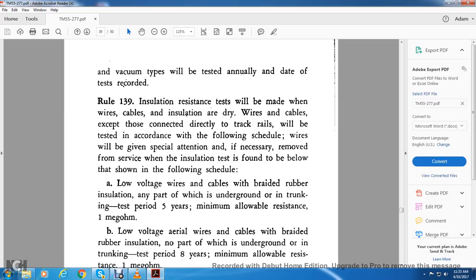Rule 139, insulation resistance testing. Insulation resistance tests will be made when the wire and cables, and insulation are dry, except those connected directly with the track rails, will be tested in accordance with the following schedule. Wires will be given the special attention necessary. Where insulation testing is found to be below the minimum, the wire will be removed from service and shown in the following schedule.